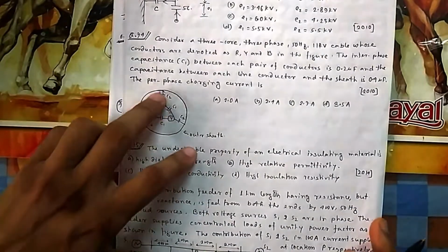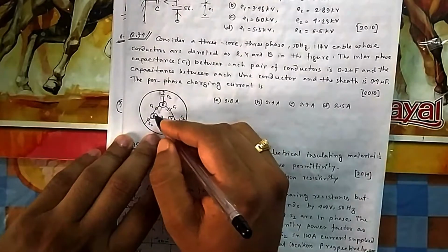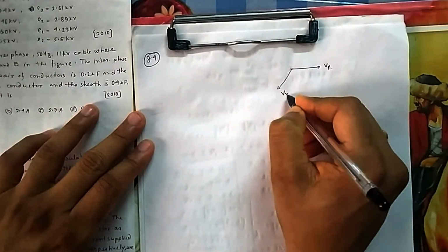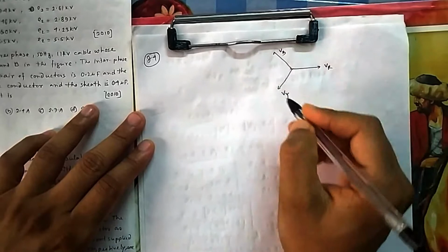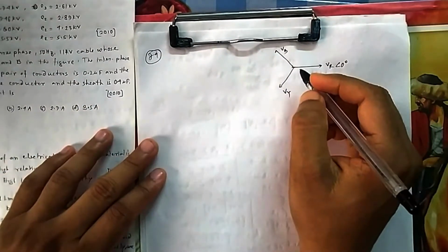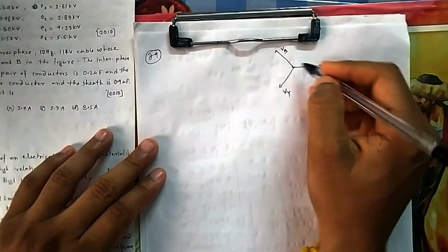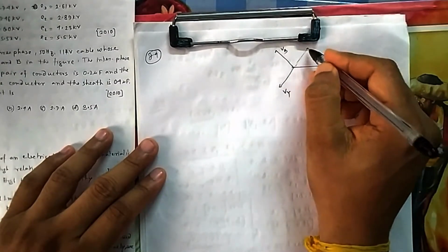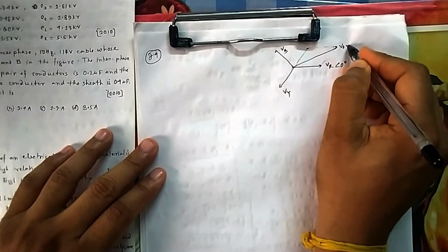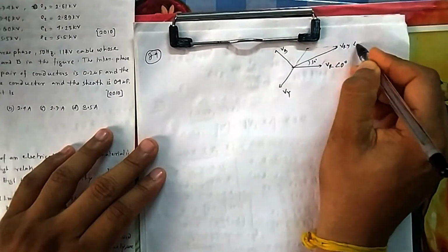So you have to draw a phasor diagram so that you have a relation between these voltages: this is VR, this is VRY, this is VRB. So this is RYB sequence. Suppose I consider VR and then VY, these are phase voltages. So one is VR, that is VR at angle 0. Another one I need is VRY. So this will be VRY leading with an angle of 30 degrees, and the magnitude will be root 3 times this.